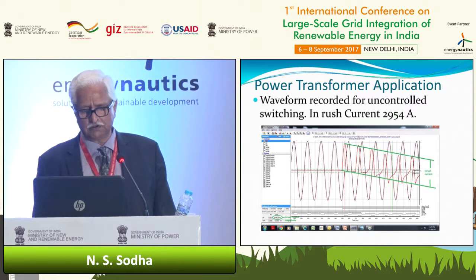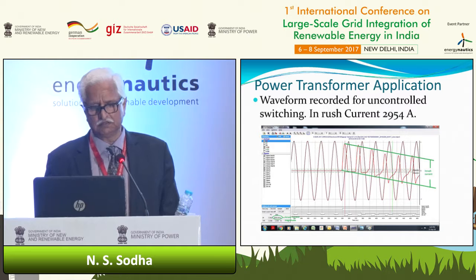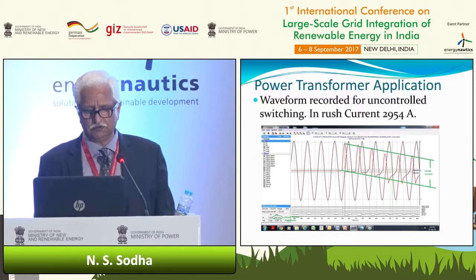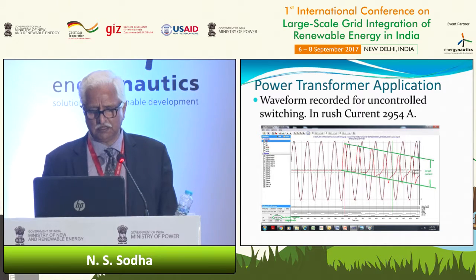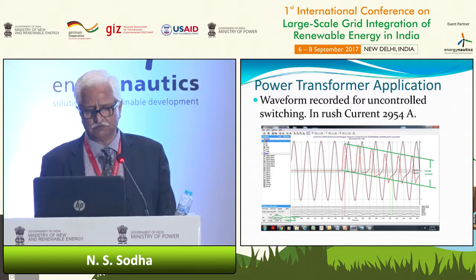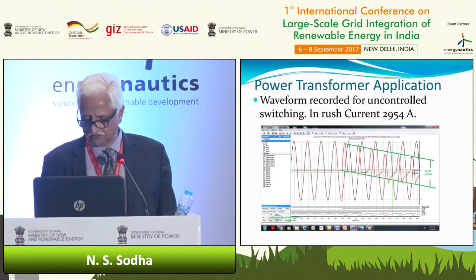Now the power transformer, without using control switching, had inrush current, and uncontrolled switching was causing close to about 3000 ampere. And you can see the waveform also, which is drooping down, and there are deviations in the waveform.